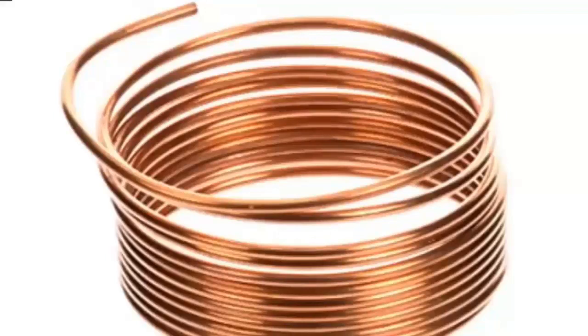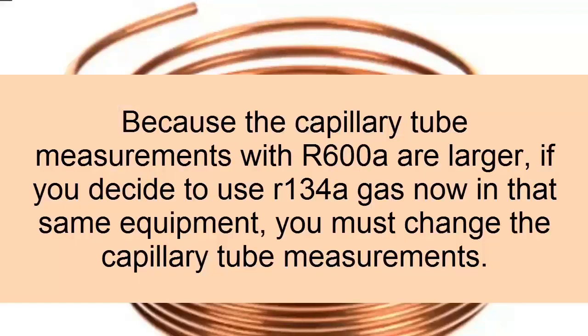Second, in case of using a R600a compressor with R134a, and the characteristics of the capillary are not changed, the compressor will be forced, since too much refrigerant will enter its suction, increasing electrical consumption.